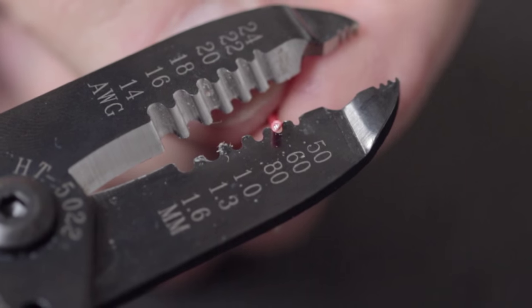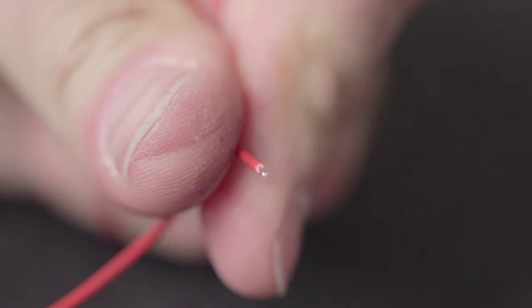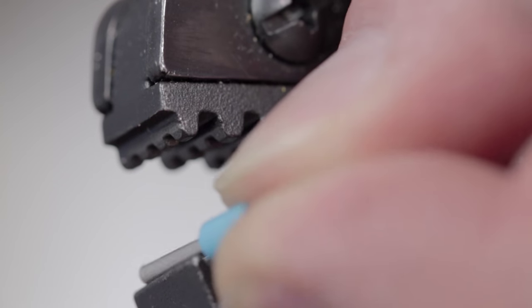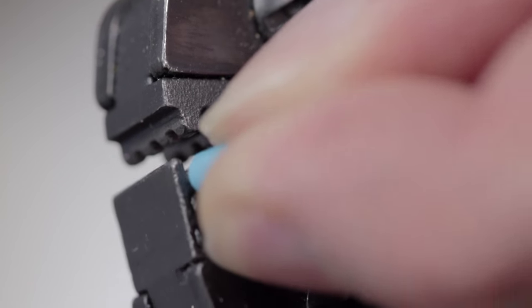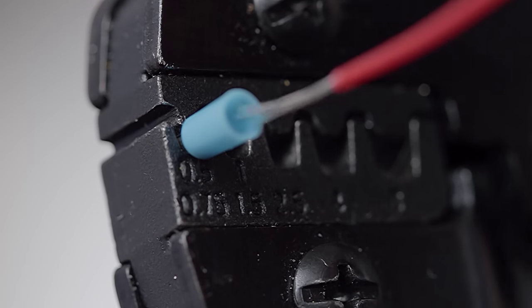First strip a 15 millimetre length of insulation off the wire. Insert the crimp into the appropriate size slot in a boot lace crimping tool and then insert the end of the wire without twisting it.